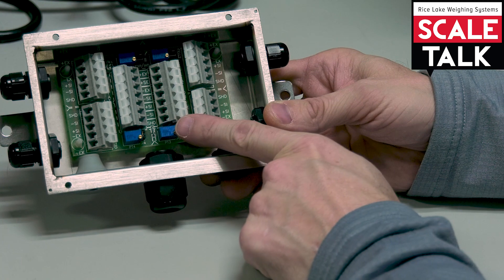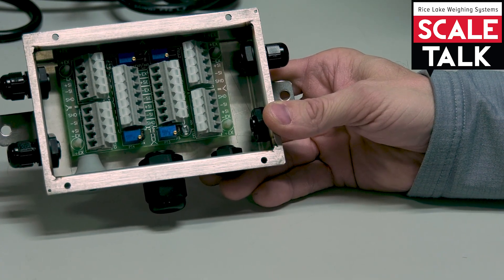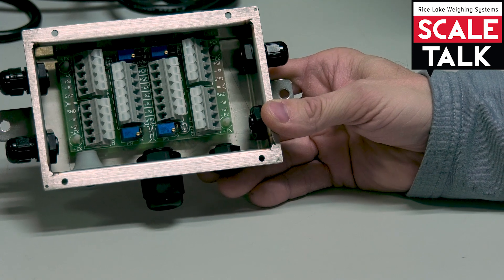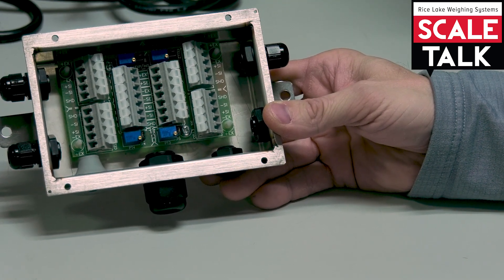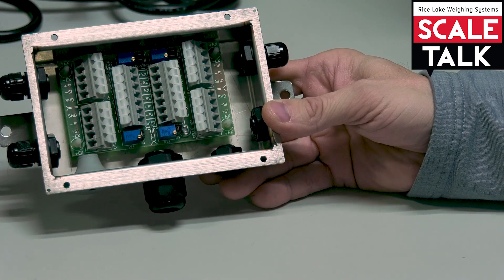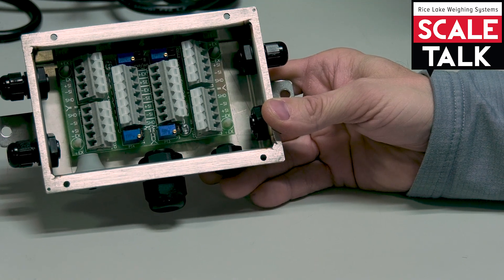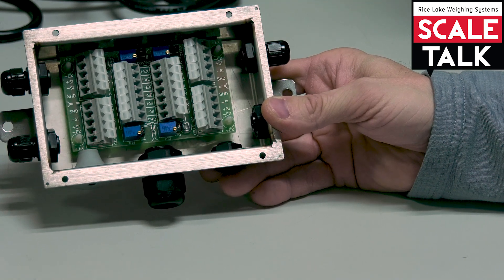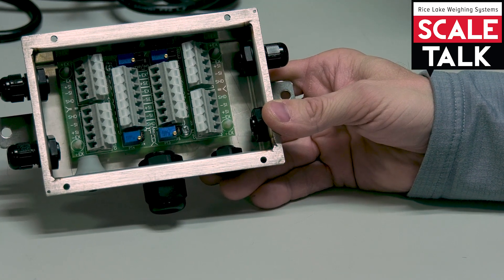The other connection block here is for an expansion. So I could daisy-chain a couple of these four-channel J-Boxes together for an eight-channel scale. For example, a truck scale might have eight load cells in it, so I could daisy-chain a couple of four-channel J-Boxes together to bring all of those load cells to function as a single system.